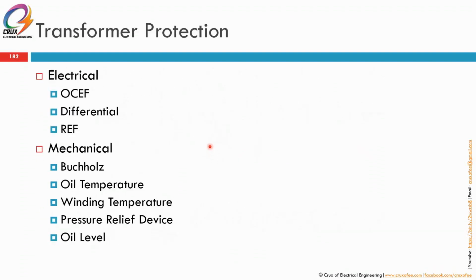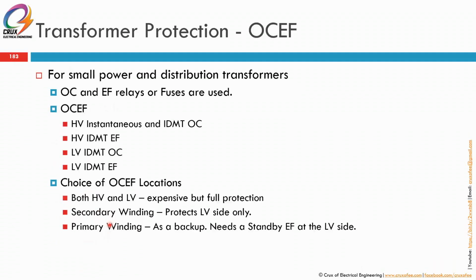transformer protection. So, there are two parts to transformer protection. We have the electrical protection and also the mechanical protection. Electrical is the normal overcurrent fault. Can be IDMT and instantaneous or both. Differential relay and also the restricted earth fault, which focus on the differential protection of the secondary winding or the star winding lah. Okay, and then mechanical, we have Buchholz, oil temperature, winding temperature, pressure relief device, and also oil level lah. These are all the typical mechanical protection that is available lah. So we'll look in a brief one by one.